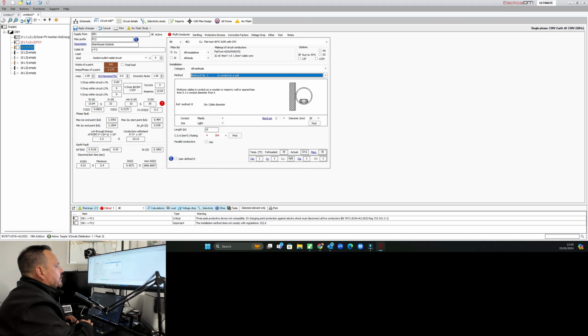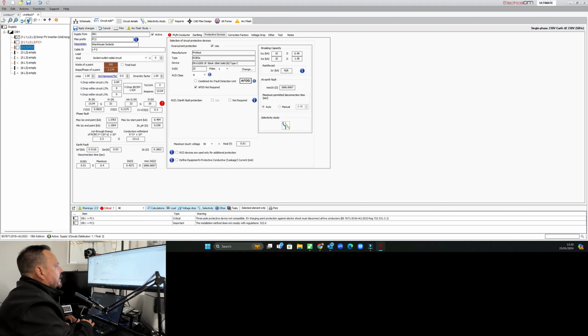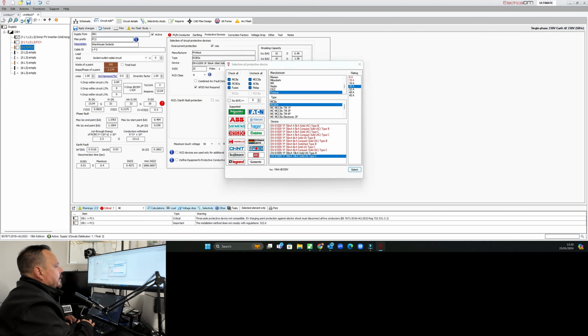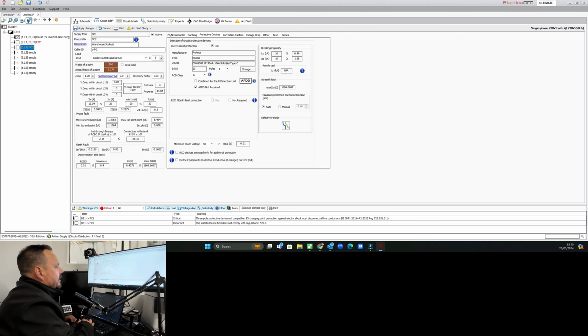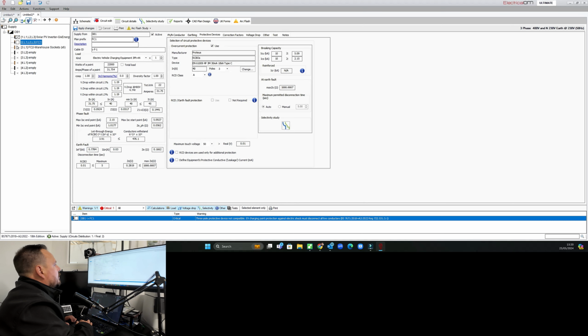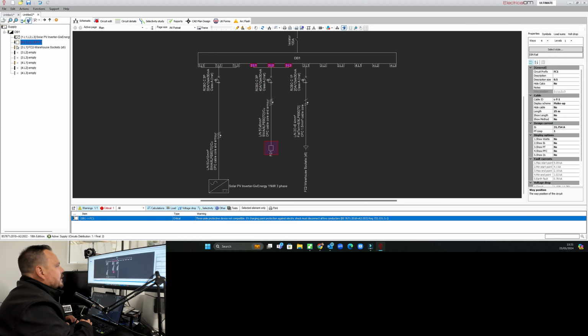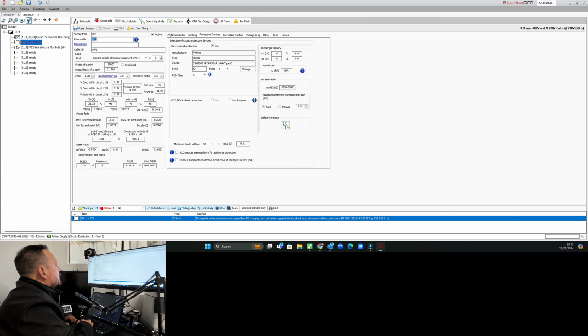But we'll stick with the in conduit on a wall, and what we're going to do is just drop the value of our protective device down to a 20 amp breaker, because we don't need that 32 amp rating for the sockets. There's nothing of real high power consumption. It is more just spreading out somewhere they can plug a bit of equipment in. So we've got that on there as well now. I have noticed a little warning that has popped up on this one, so we'll see what that warning is related to. I suspect it'll be an isolation point somewhere. Let's go back and look in the schematic. So we've got our RCBO, which is in there. It's 40 amp 10 kA rating. We've got our 5 core. What's this little thing here? Let's have a look.